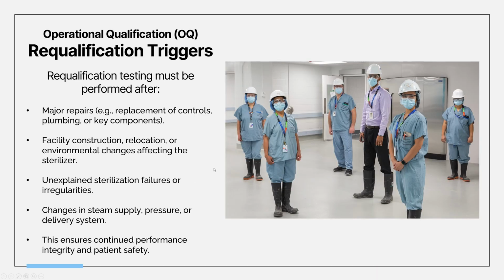Requalification testing must be performed after major component repairs. So let's say valves or controls were changed, or there's been construction or relocation. If you look at this picture, this was actually Mount Sinai after they had major construction. This was when they had new sterilizers and everything. So they had to go through this whole process to ensure that the hospital MDRD meets regulations and standards.